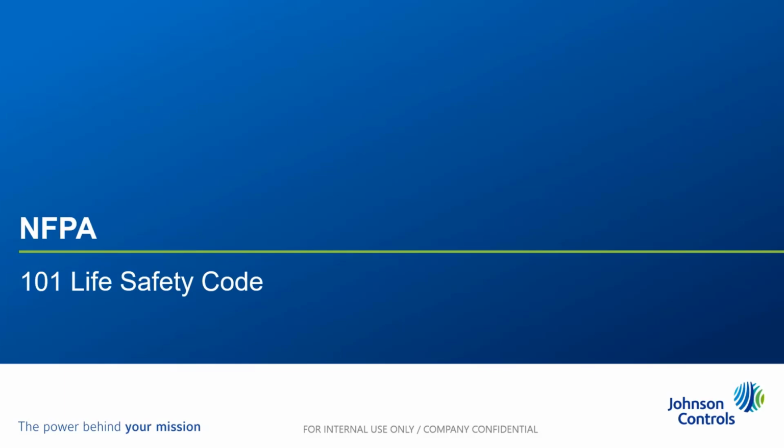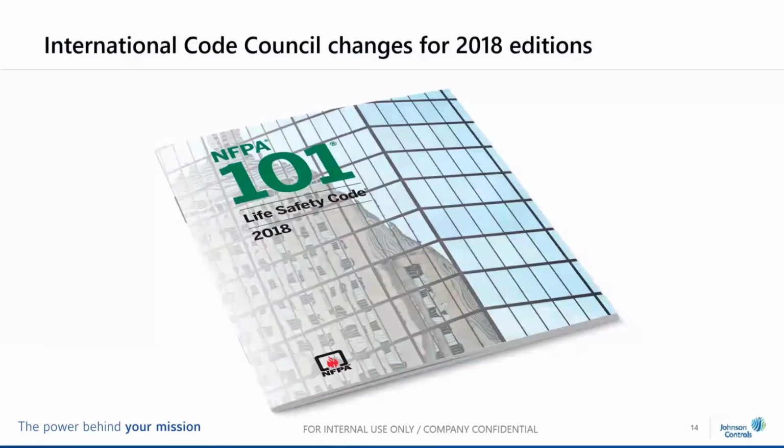But there's still confusion as I go around, with people asking how NFPA and the I-codes work together or not work together. Well, in many respects, they're competition to one another. However, the I-codes don't write standards, so they reference back to NFPA for their standards, like NFPA 13 for sprinklers and 10 for extinguishers and so forth. So the building code for NFPA is 101, the Life Safety Code. And coincidentally, you have the 2018 edition as well.